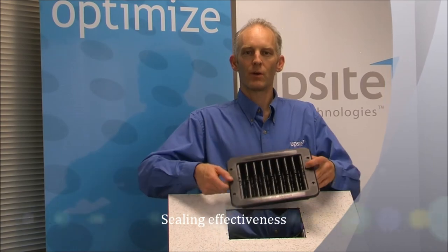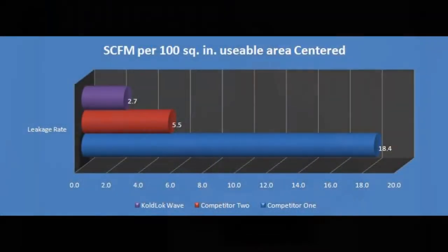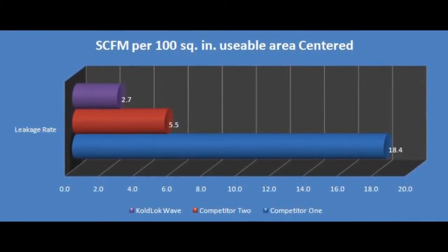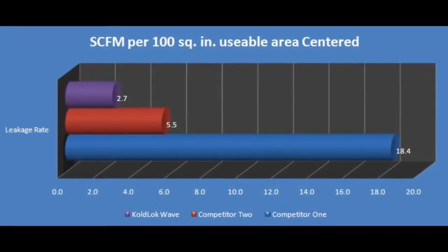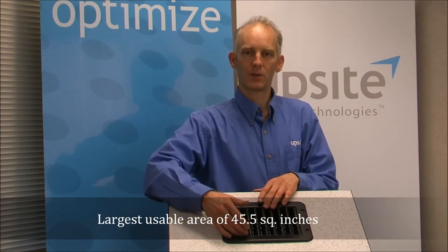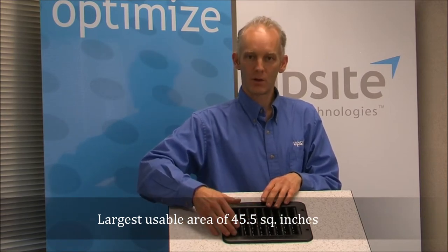Following is a sample of some recent test data showing the relative performance of some popular grommets. This data was taken at a static pressure of 0.05 inches of water column. Here are the results for the sealing effectiveness of the KoldLok Wave. The way that the thermoplastic elastomer is over-molded to the ABS frame creates a very large usable area. The usable area of a KoldLok Wave is anywhere from 35 to 169% more than other grommets in the market.